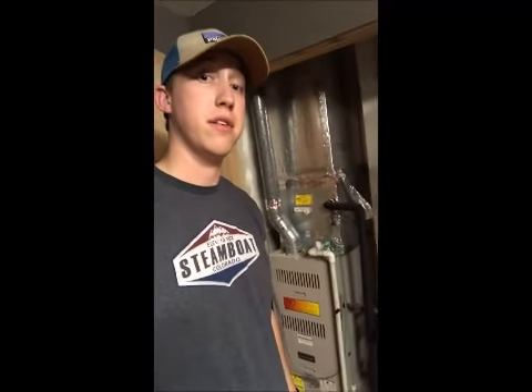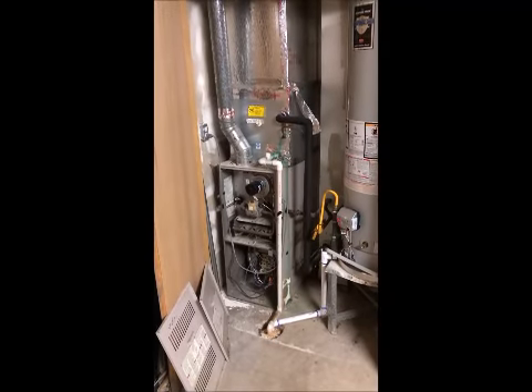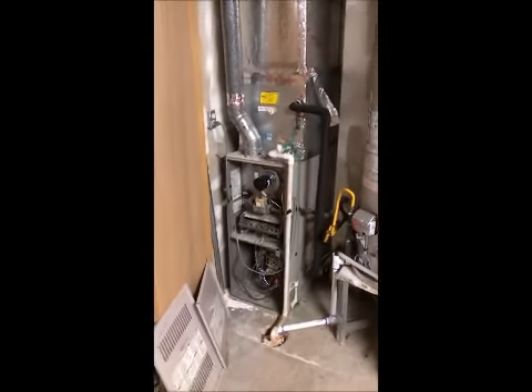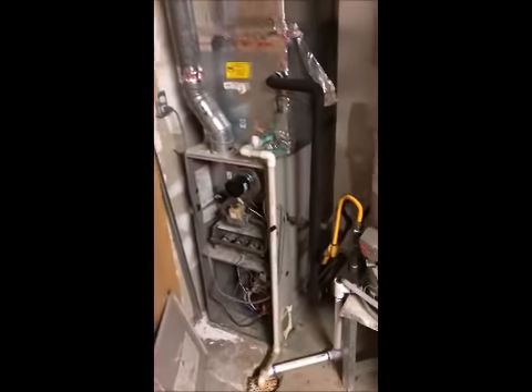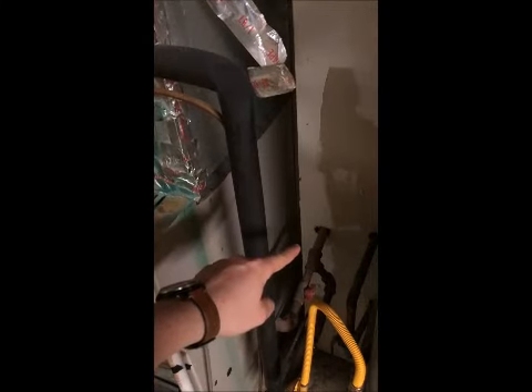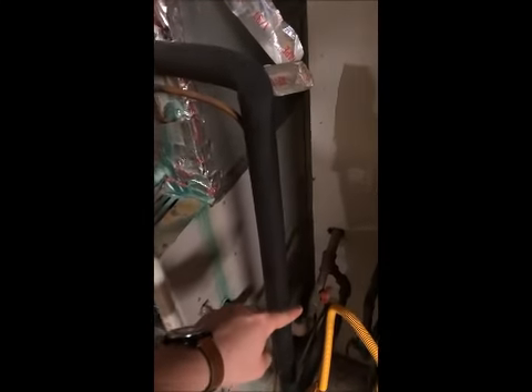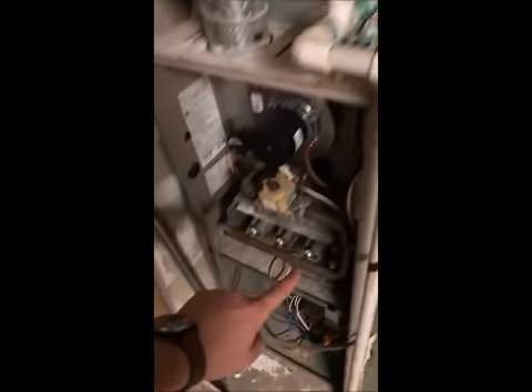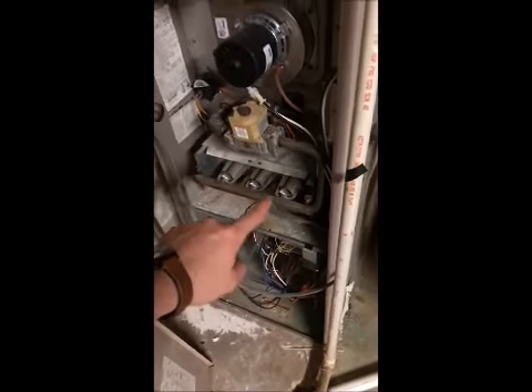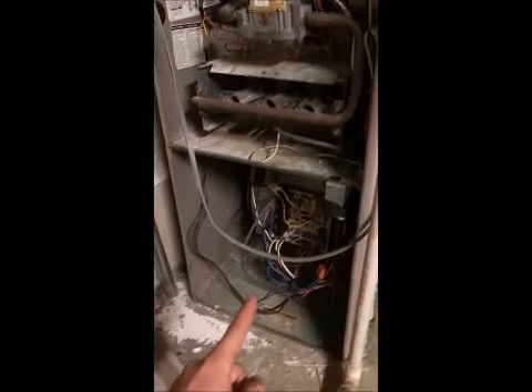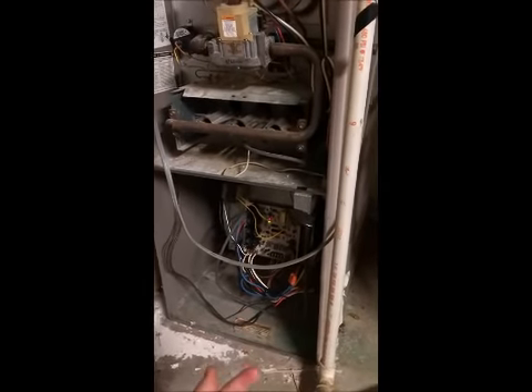Now I'm going to take apart these panels here. I'm going to show you all about the furnace. So here is your Concord 80 plus furnace. It gives off about 60,000 BTUs. It is a gas powered furnace, so you got your gas line coming in right here. You got your on and off valve, gas line going in here, supplying the flame, which then warms up the air.